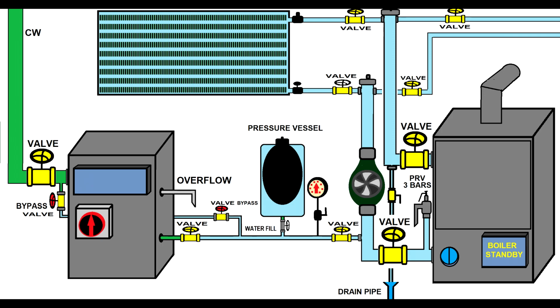Because you don't want to stress the pressurization unit's pumps when you fill the system for the first time, you will use the bypass. You will see in this small footage that the bypass valves are pulsing, changing from yellow to red. Also, the purge valve is pulsing, you have to open the purge valve to complete the water circuit. You'll hear the air eliminator working for a while, and it will work until the entire amount of air is eliminated from the heating system.